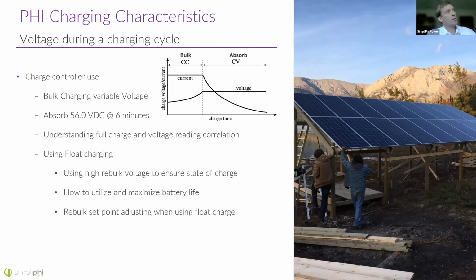Now, there is an additional cycle for lead acid batteries. There's a float as well. So if you have a renewable energy source, you might want to float your batteries, and that'll just ensure that the batteries stay charged at 100% state of charge. The voltage for that is not listed here, but it's 54 volts for a system. You don't want to float the batteries if you're using something like a grid-tied system because it's kind of a waste of energy. You're not really putting much into the system.